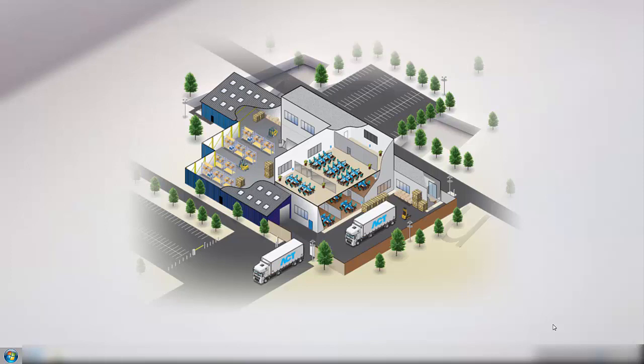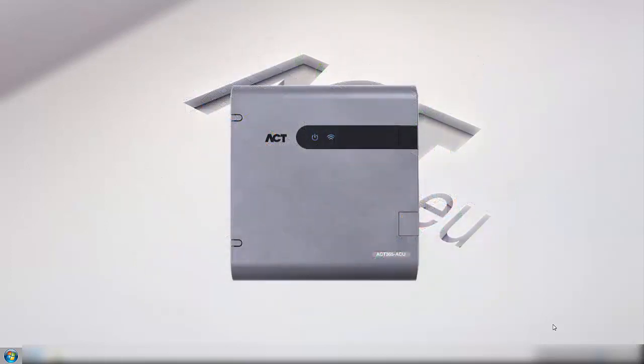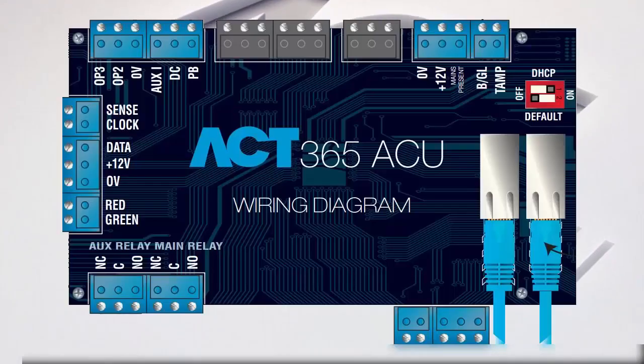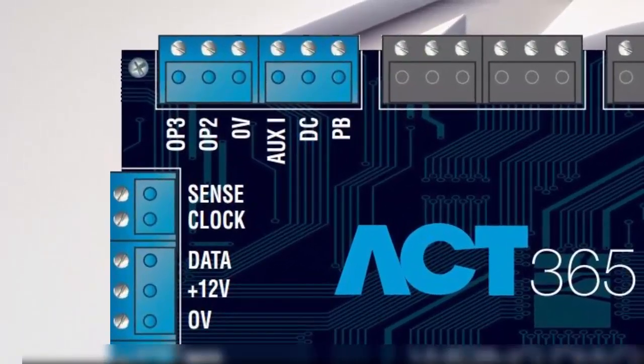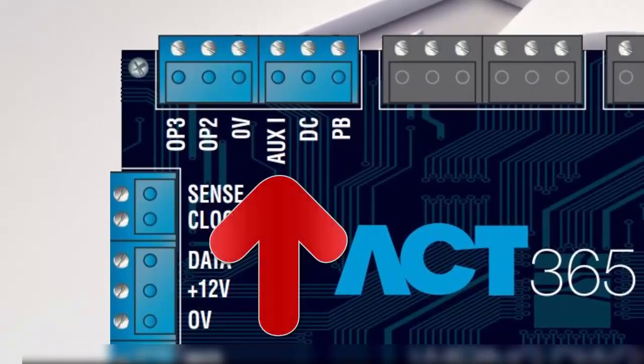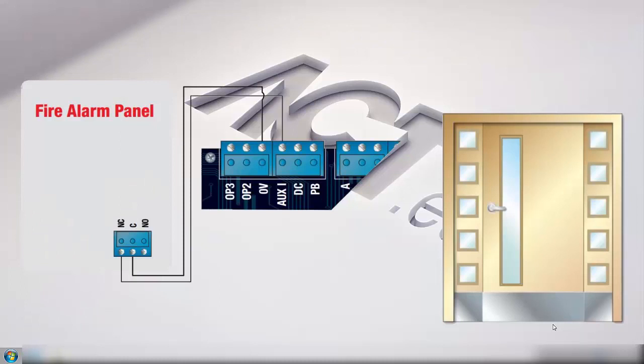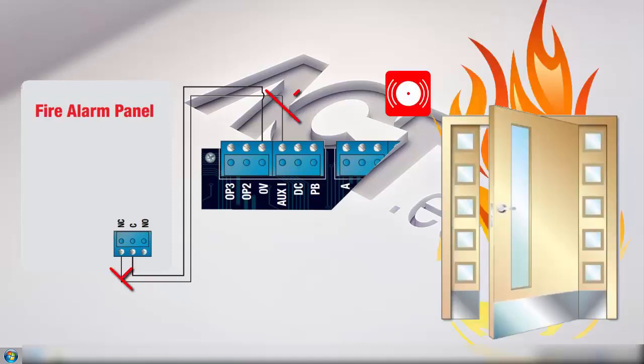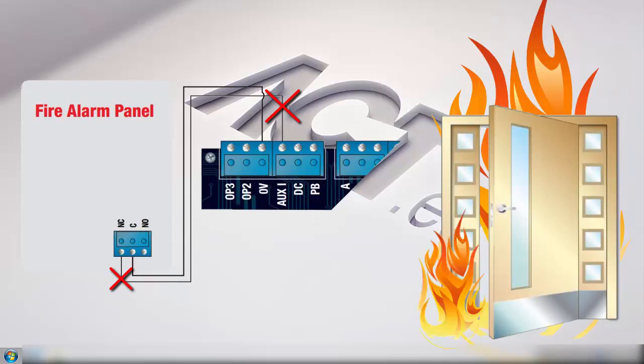Firstly, let's look at the wiring. Every ACU defined as a fire override door requires a wired link back to the fire panel. The ACU is looking for a continual 0 volts on auxiliary in terminal for a normal state. When a fire is activated, the normally closed relay on the fire panel goes open, breaking the 0V into auxiliary in. Once this is removed, the controller knows a fire has occurred and will unlock the door. The door will not normalize until the fire panel is reset and a 0 volt applied once more to the auxiliary in terminal.